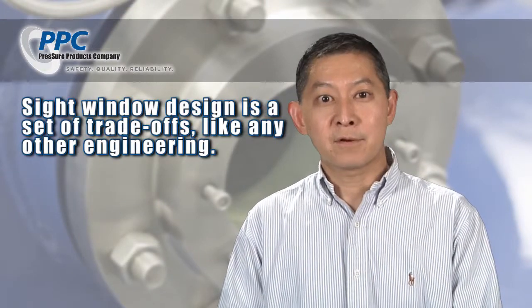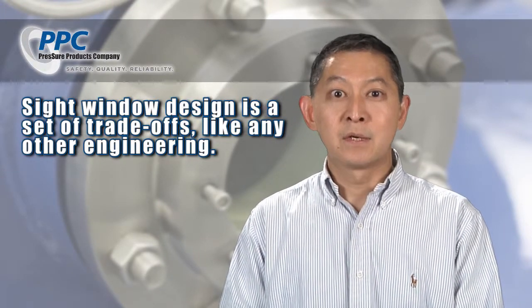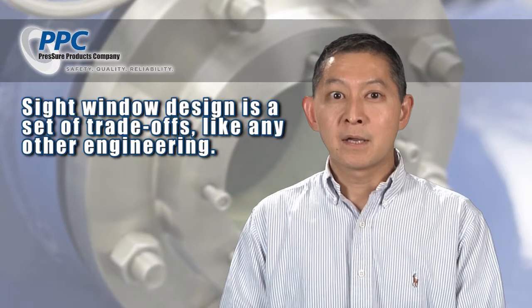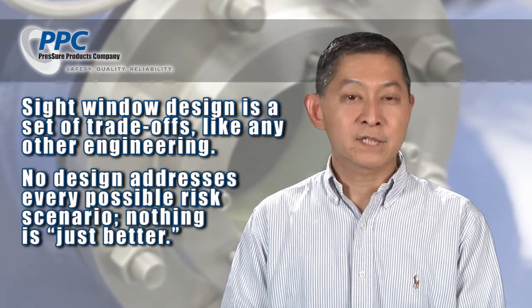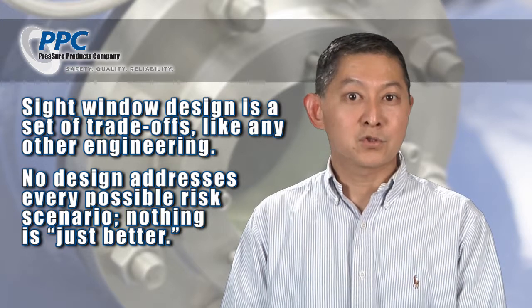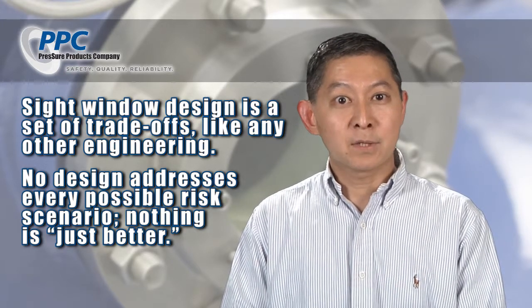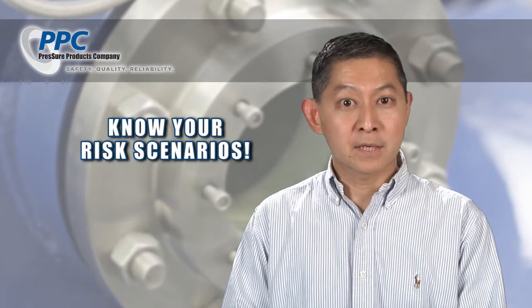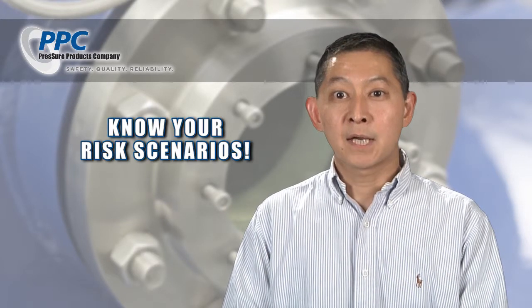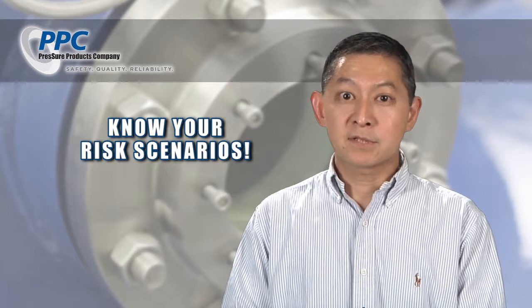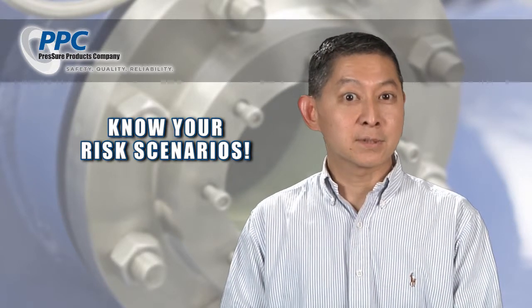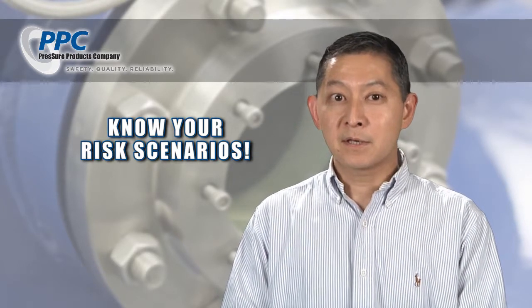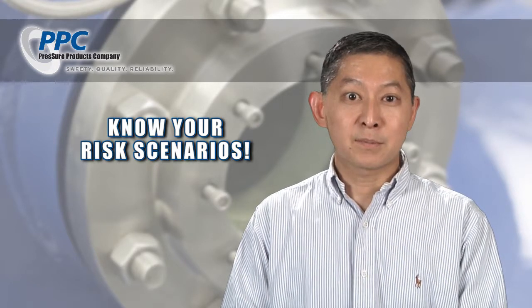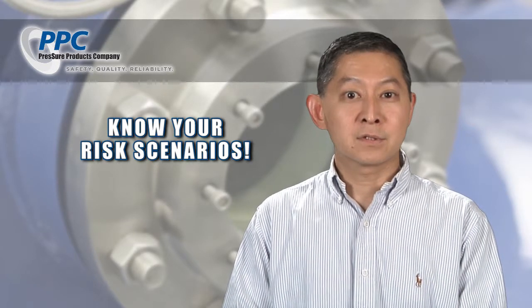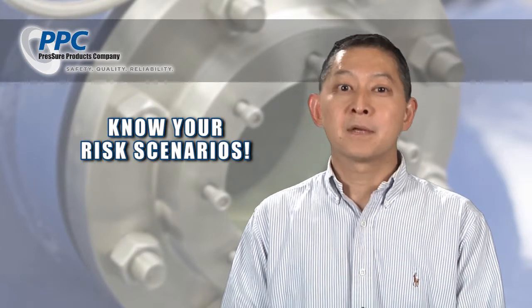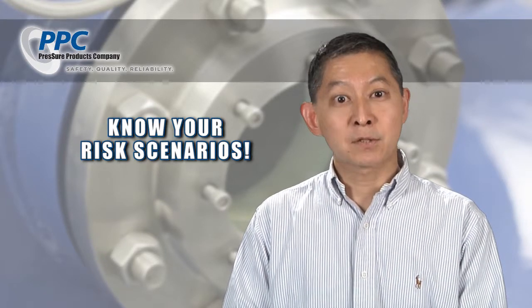As in every other area of engineering, sight glass window design is a combination of trade-offs, and there is no design that addresses every risk factor. There is nothing that's quote-unquote just better. So when you specify sight windows, think about the causes for pressure spikes, why your process is pressurized, and what your risk factors are. If you get your sight windows from us, our sales engineers are supposed to ask about these, but ultimately, it's your process, and you'll be stuck with the product. So you want to make sure that you understand those risk factors quantitatively, and that you specify your sight windows with respect to those risk factors.